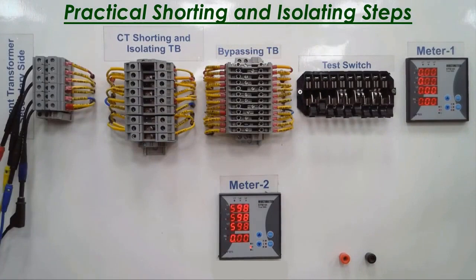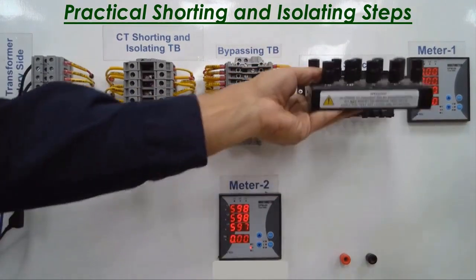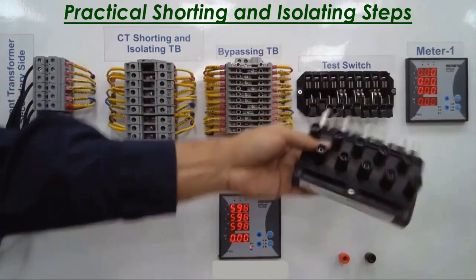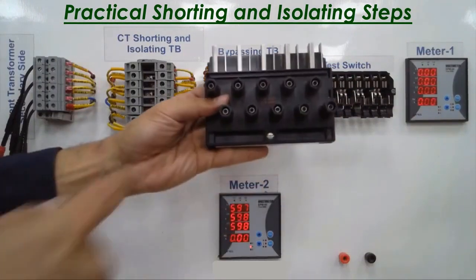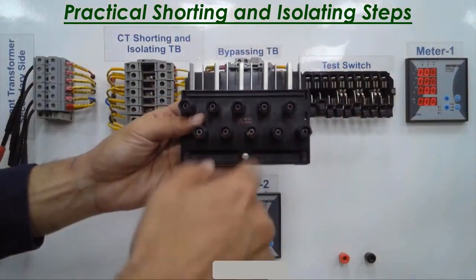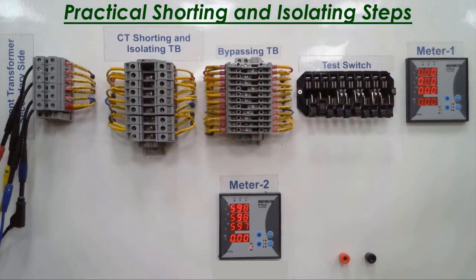Did I do isolating? No, I didn't do isolating. We agreed that to do isolating, you need to bring your test plug and ensure you are entering the test plug here to isolate the first power meter, and ensure you connect your test leads here to test your power meter, or if it was a protection relay.